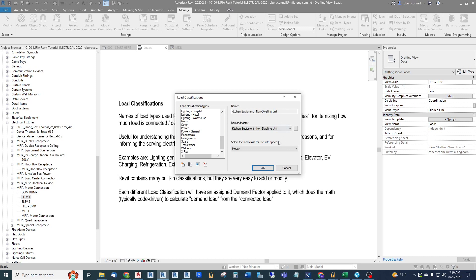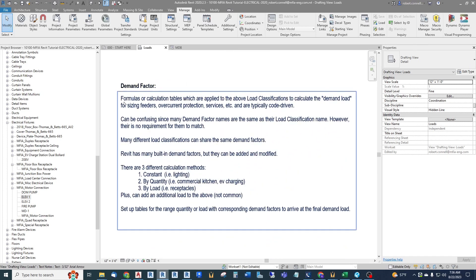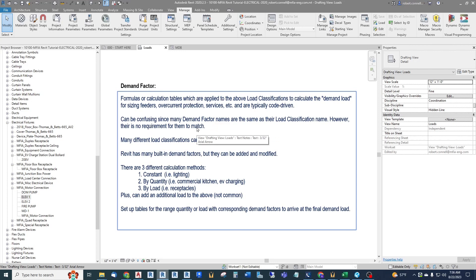Demand factors are the formulas or calculation tables applied to load classifications to calculate the demand load for sizing feeders, overcurrent protection, services, etc. They are typically code-driven. Many demand factor names match their load classification name — like kitchen non-dwelling — which can be confusing, but there's no requirement that they match. For example, a lighting load classification could use a demand factor called 'continuous load' representing 125%.